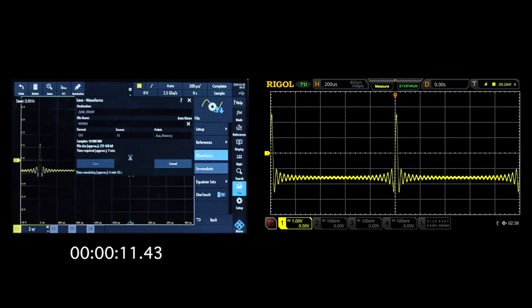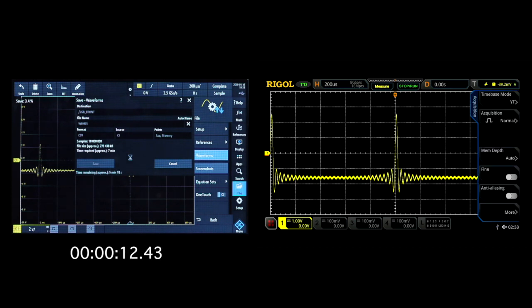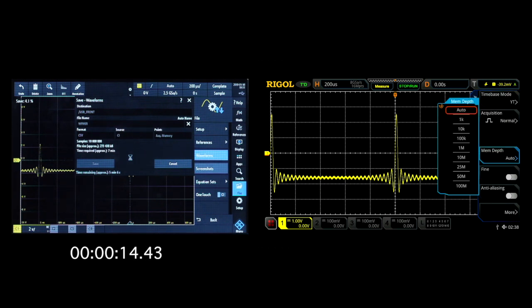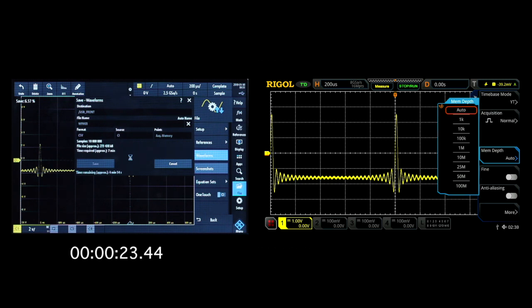To begin, just like before, we're going to go into the acquire menu and select our memory depth to be 10 million points. We're now going to see the instrument save the same 10 million point file to the flash drive as well.